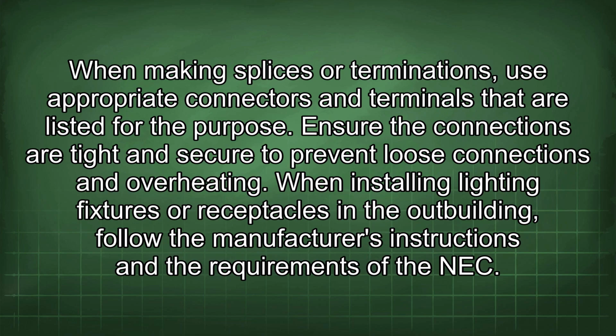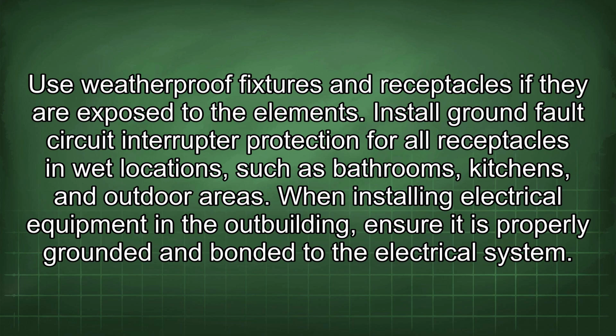When making splices or terminations, use appropriate connectors and terminals that are listed for the purpose. Ensure the connections are tight and secure to prevent loose connections and overheating. When installing lighting fixtures or receptacles in the outbuilding, follow the manufacturer's instructions and the requirements of the NEC. Use weatherproof fixtures and receptacles if they are exposed to the elements.